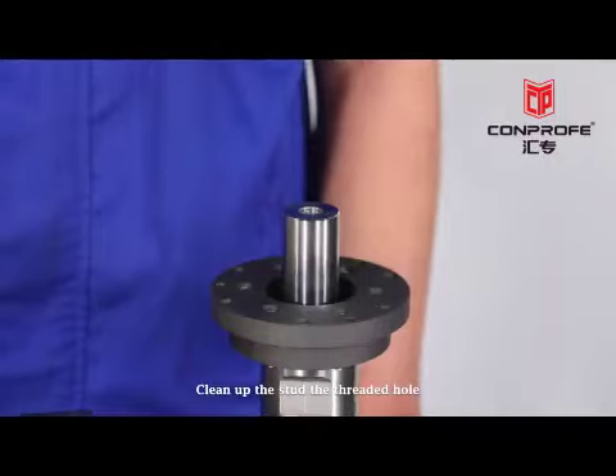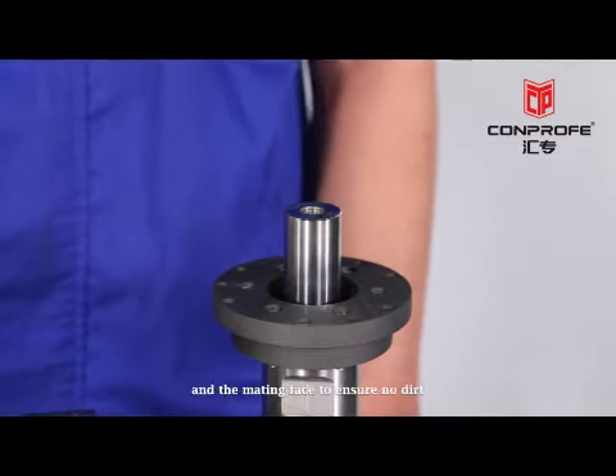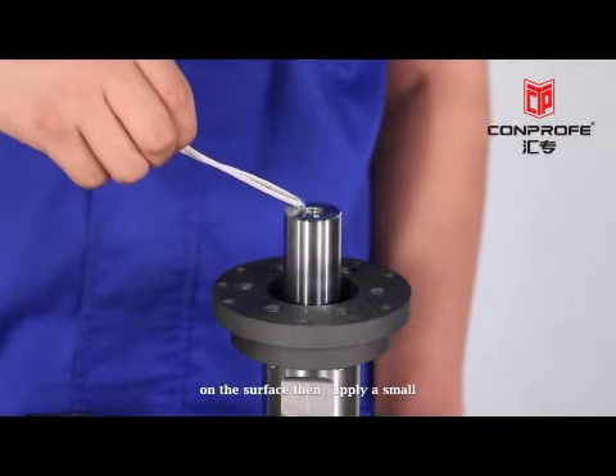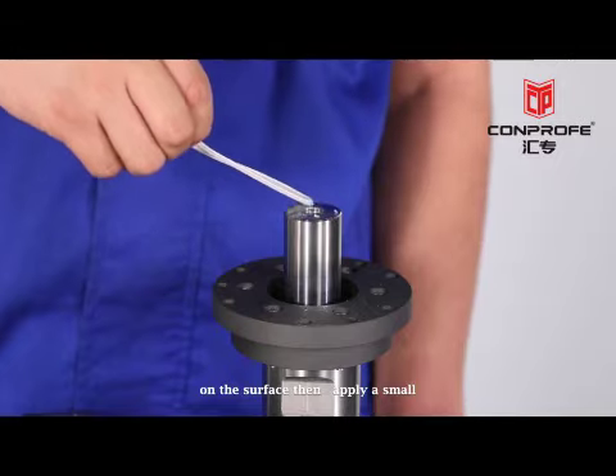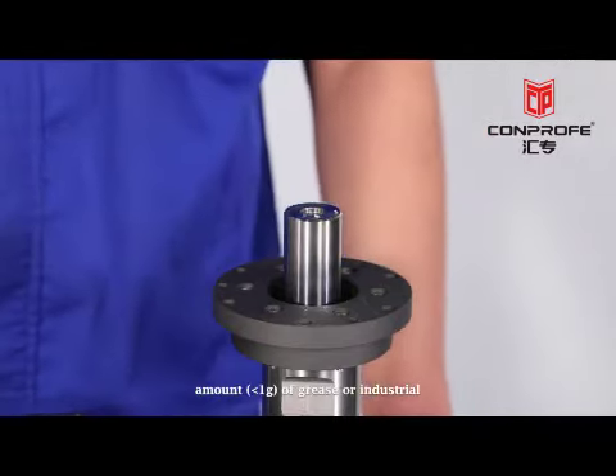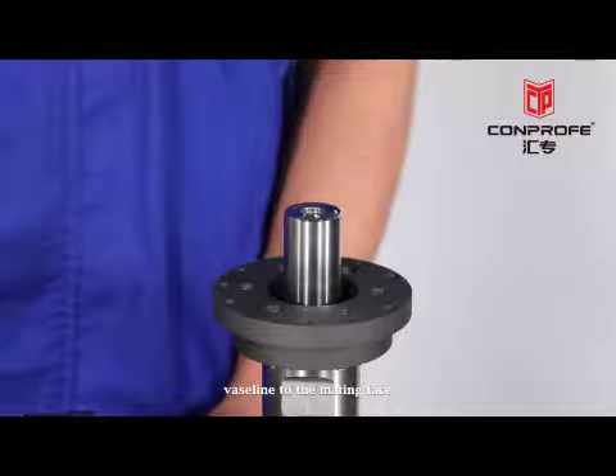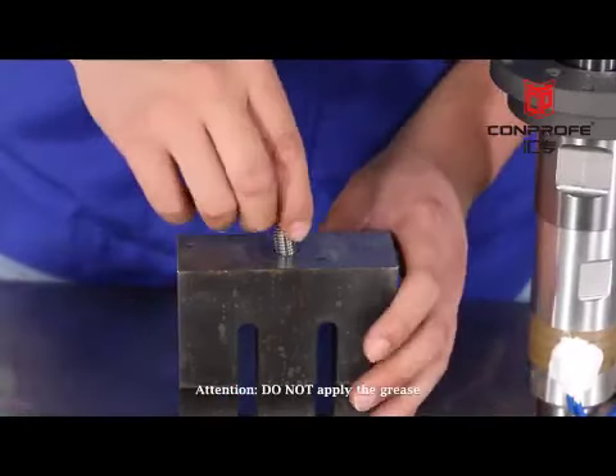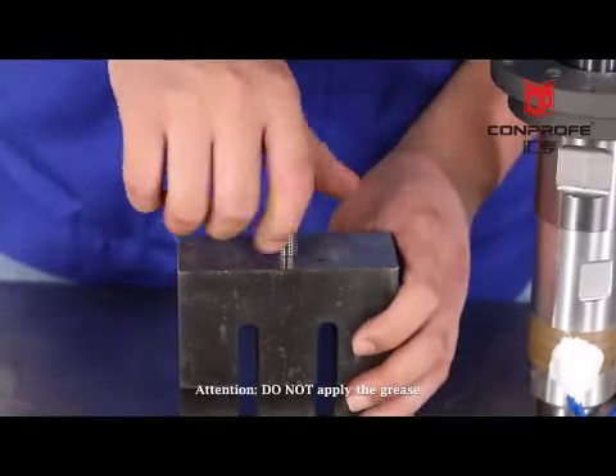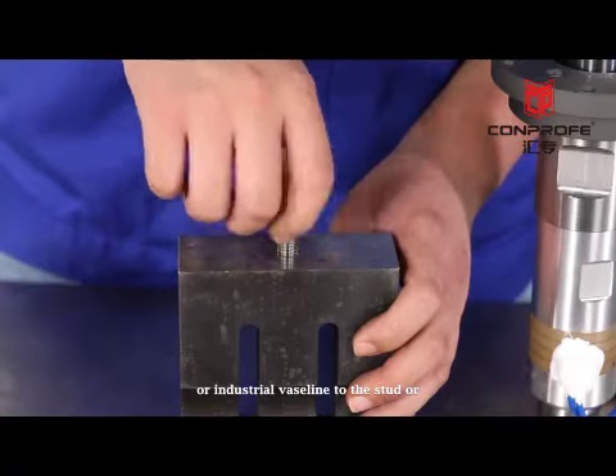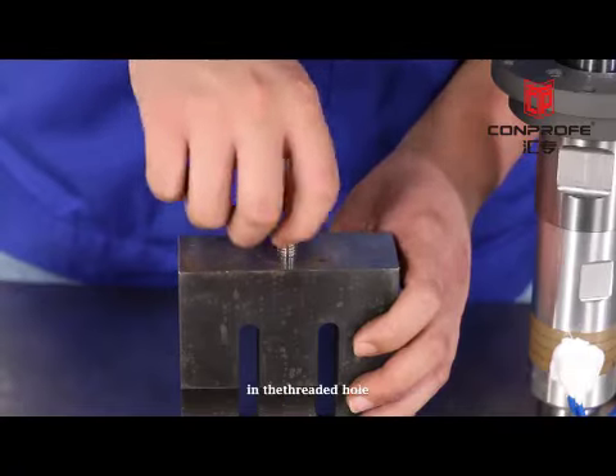Precautions for welding head installation. Clean up the stud, the threaded hole and the mating face to ensure no dirt on the surface. Then, apply a small amount, less than 1 gram, of grease or industrial Vaseline to the mating face. Attention! Do not apply the grease or industrial Vaseline to the stud or in the threaded hole.